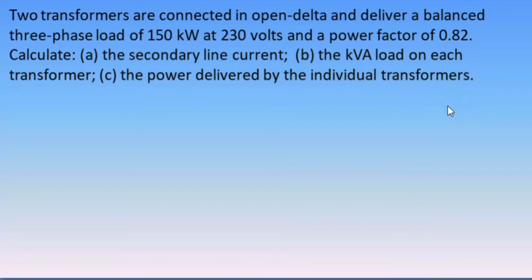Again, it is very important to solve similar problems so that we would be familiarized. And in that way, we could easily understand and remember how to solve this kind of problems. So we have an open delta system delivering a balanced load of 150 kilowatts at a voltage of 230, and its power factor is 0.82. Letter A, determine the secondary line current.